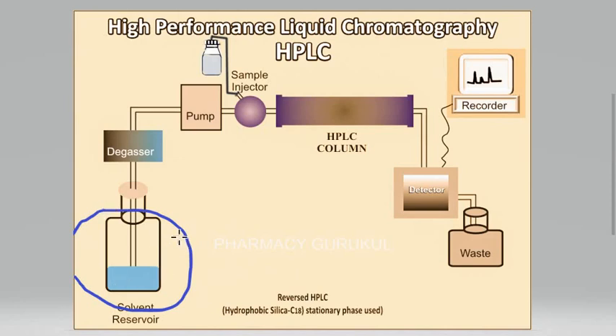This is the solvent reservoir. This is the place from where HPLC starts. This reservoir contains solvent used to carry the sample through the system. The solvent inside solvent reservoir contains about 90% water and 10% organic solution.